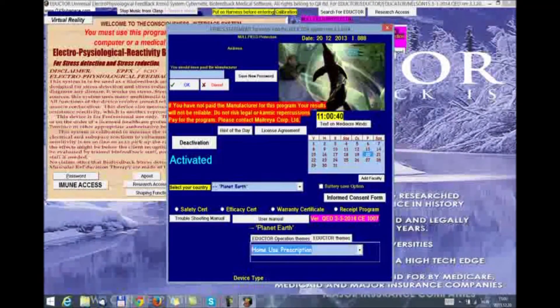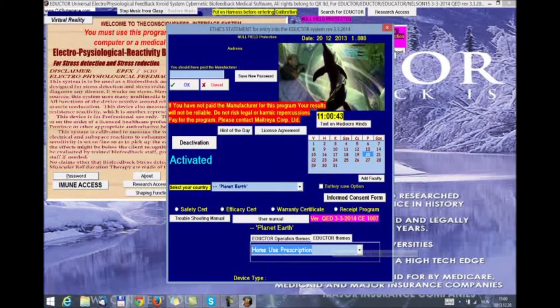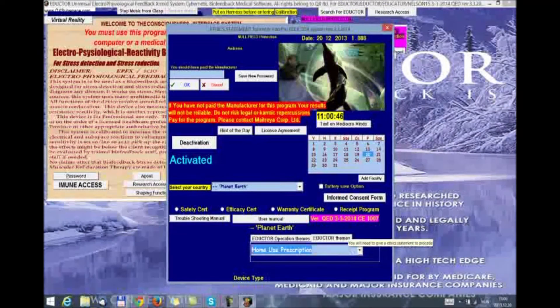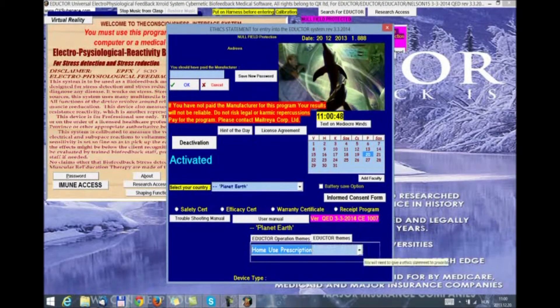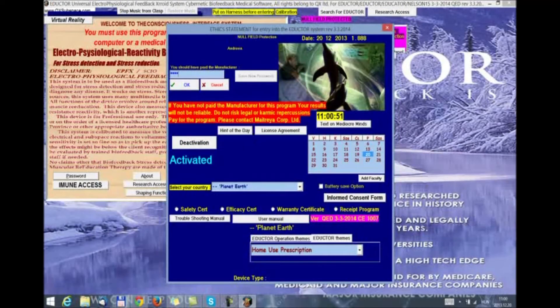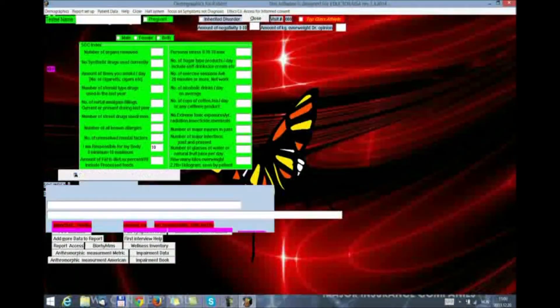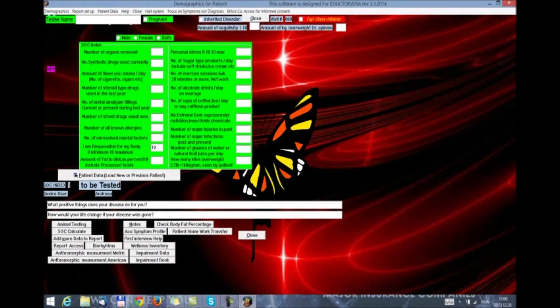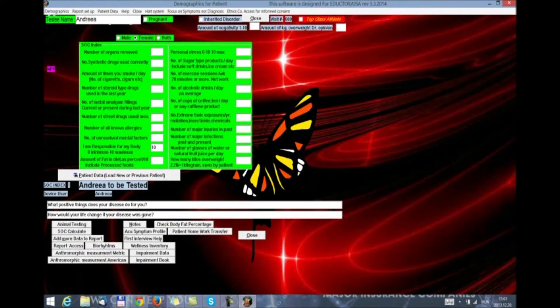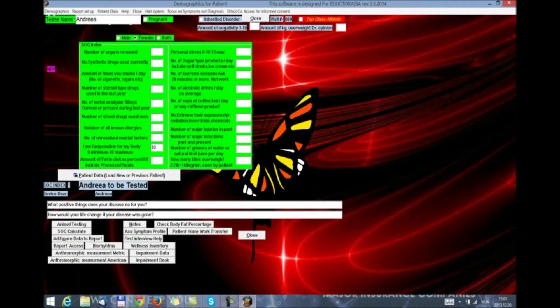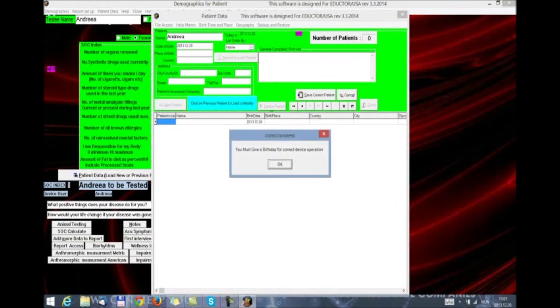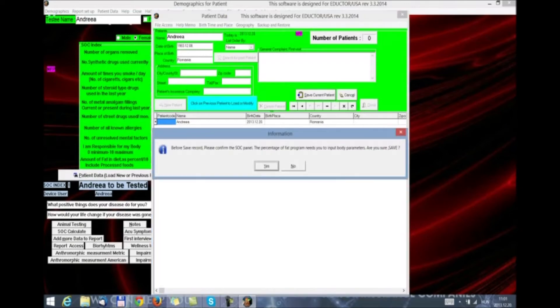So, if you just want to use the eductor themes and all of the rest of the program, please click on home use prescription from this button. So, we have selected home use. We are going to enter the password 0210. Click okay. Select one patient. Create one patient because we don't have one to use. We are required to do the demographics, number of organs removed, drugs, cigarettes, and all of the rest of the questions we already know.